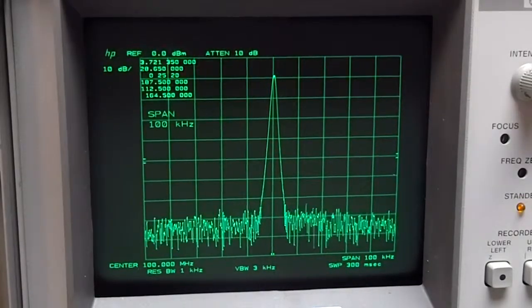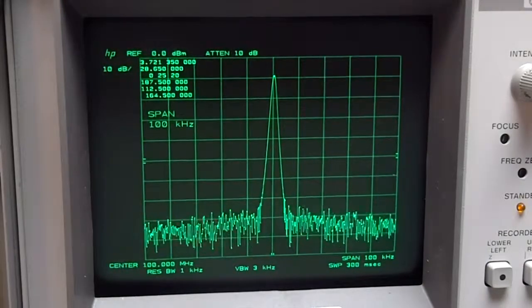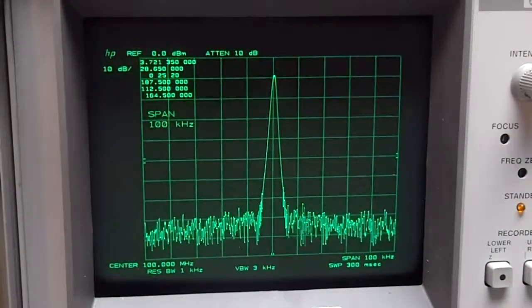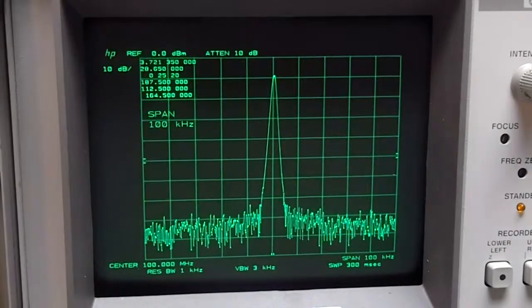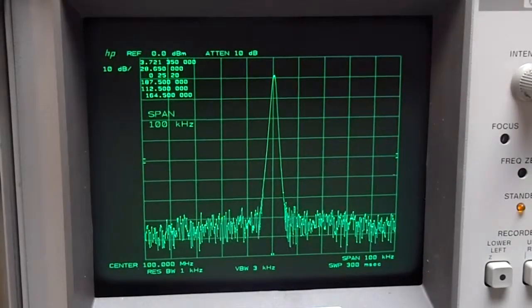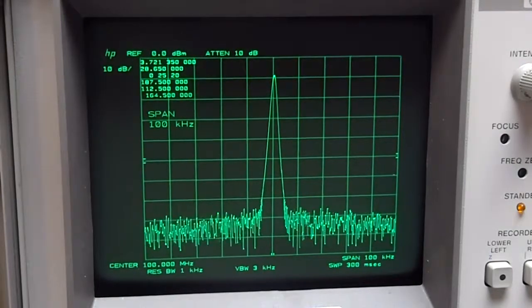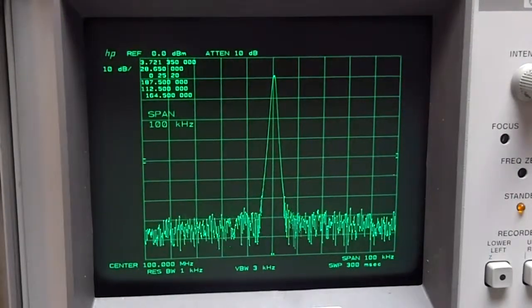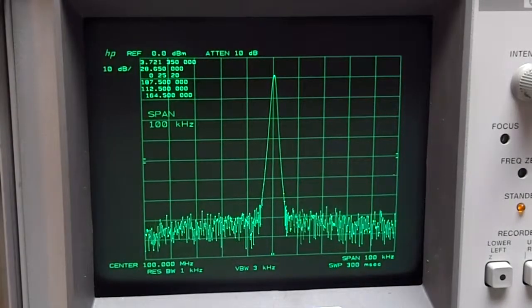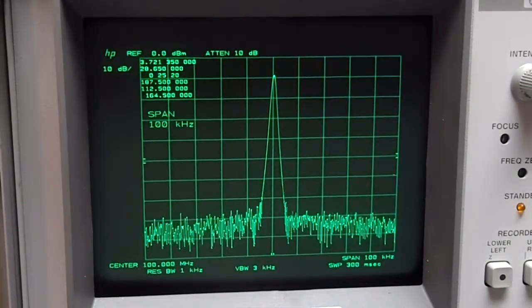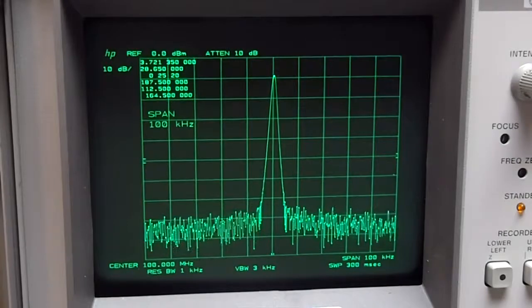So this diagnostic is very easy to use. It's access, I should say. It's 2 keystrokes. And it's very useful if you have a problem with the synthesis in the machine to double check what's coming out of the various subsystems. And you can also check the frequency of the LO by just going to your front panel here. I don't want to move my camera.